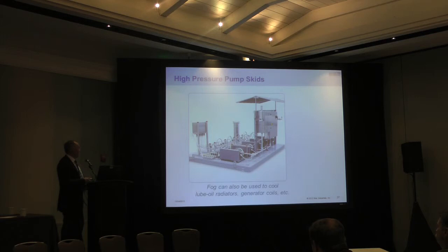That's a typical high pressure pump skid. So these are, you can't see them, but behind that belt guard there is a CAT ceramic plunger, high pressure pump, stainless steel head. That's kind of the standard for inlet fogging. More recently, Danfoss company has introduced an all stainless steel pump that has no seals and no oil in it. It's actually lubricated by water. So we're doing some work with those now also.